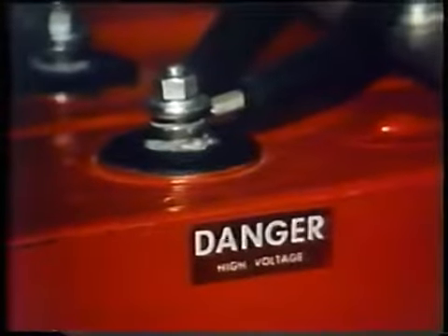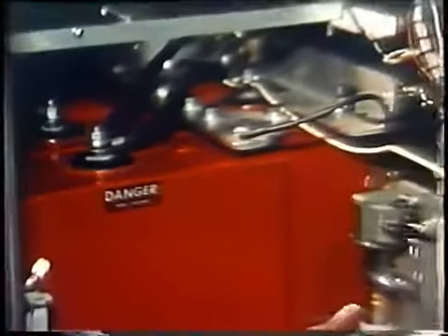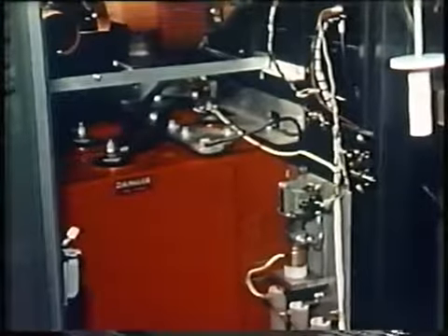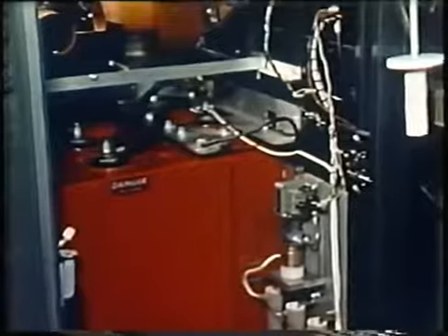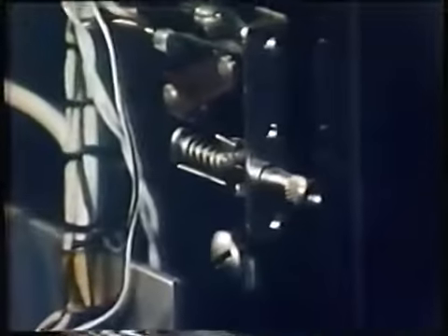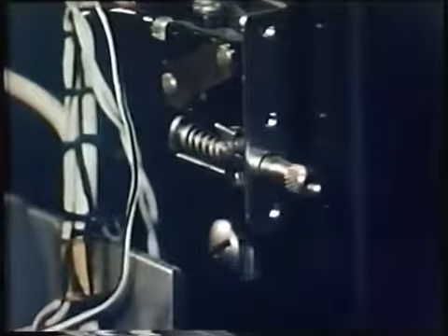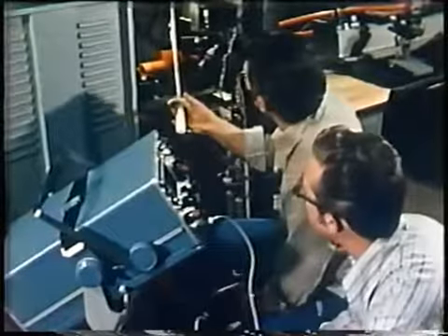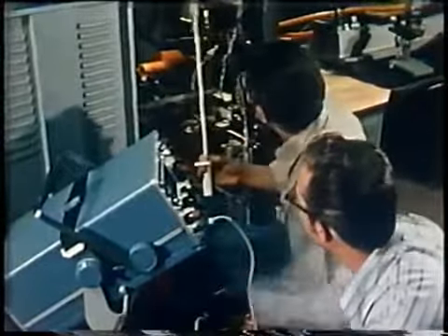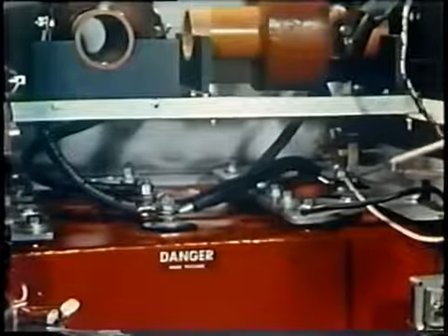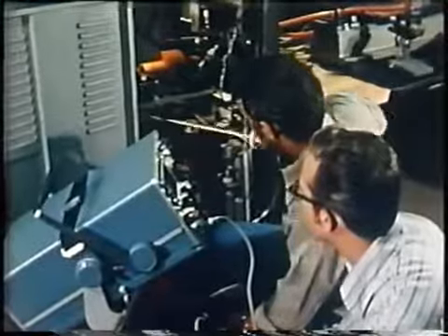The high voltages required for the operation of lasers present another safety hazard, the high voltage power supply. It is designed to be safe. When the power supply door is open, the safety interlock on the access door automatically shuts off the power supply. However, there still may be high voltage remaining, high voltage which can kill instantly. Because of this danger, maintenance should be performed by two individuals, since several manual operations may have to be handled simultaneously.